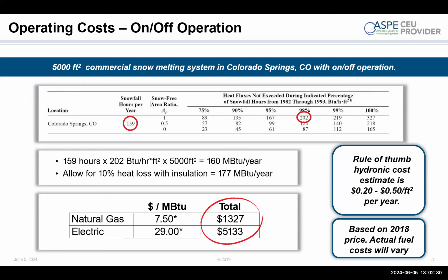That goes back to the ambulance example, having the factor of 1 where you can have no accumulation, correct? Correct. Yeah, if that is a critical factor, that the surface is entirely smooth and ice free all the time, a double serpentine may be what you want to consider from an installation standpoint.